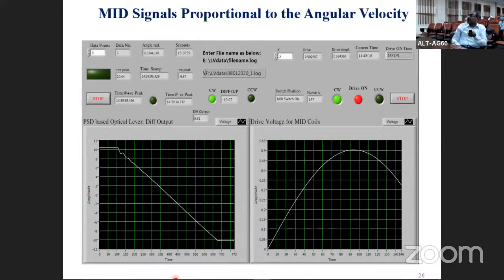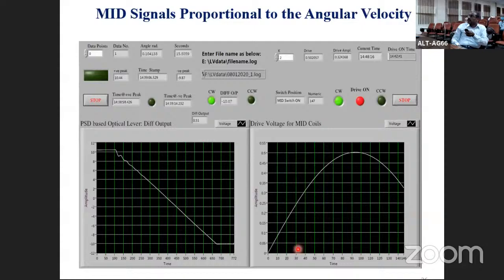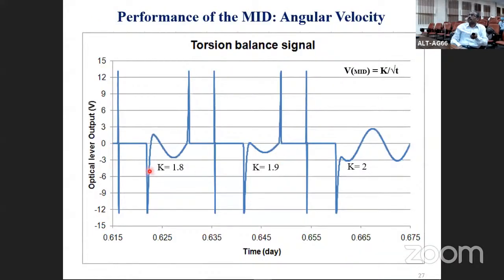In this case, the drive is applied in a half-sinusoidal fashion for a half period of the torsion balance. That is, you start at the extreme of the torsion balance position. By the time it comes to the center, it takes half the time. It is supposed to go to the extreme, but you have applied the drive torque to slow it down. So what it looks like is somewhere like this: here it was on the detector where you measure the transition time, and here you apply the drive torque.